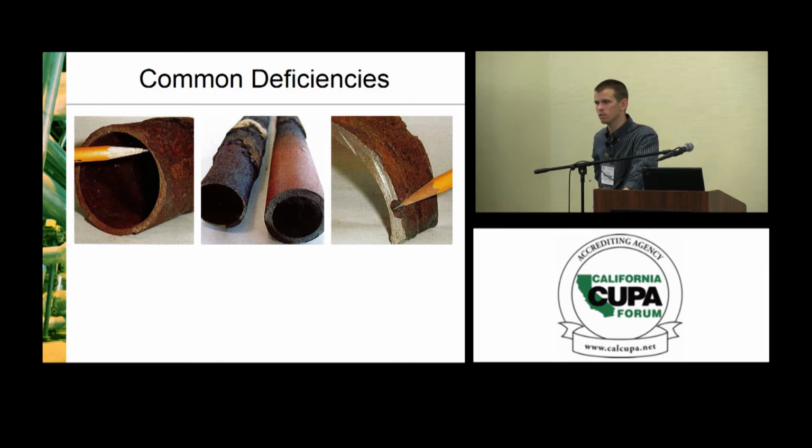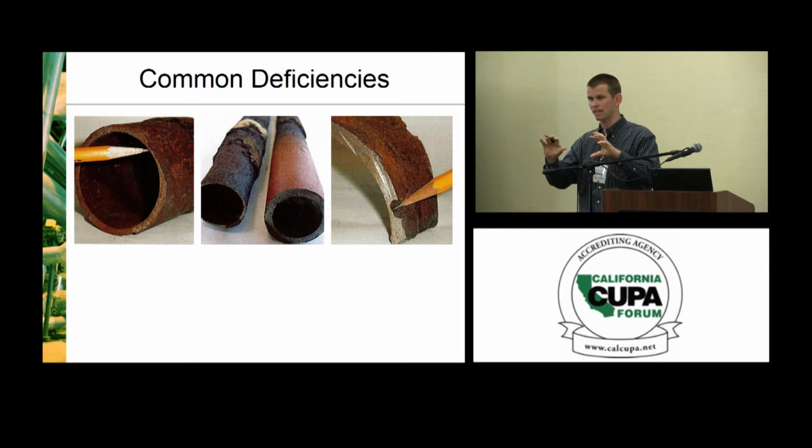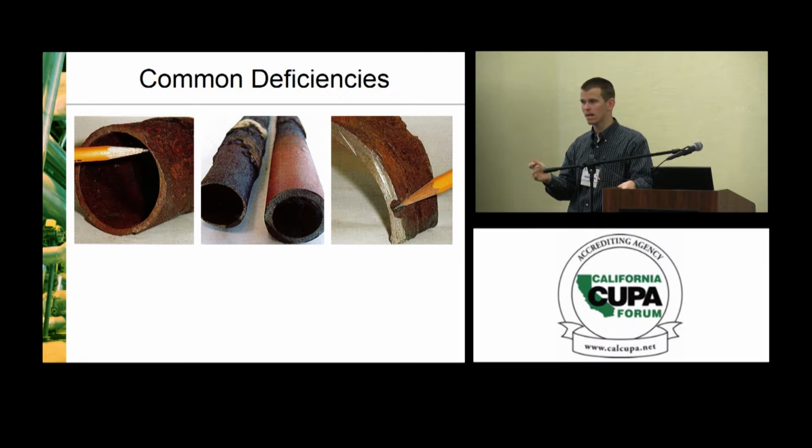So to answer your question, Michael, our recommendation is when insulation looks right, when it looks like it's in good shape, the joints are sealed, the jacketing's in good shape, all signs indicate it's fine, we don't recommend cutting into it, because then you've cut into it. And you've just made a break in the vapor barrier that you're going to have to reseal. And so forth.